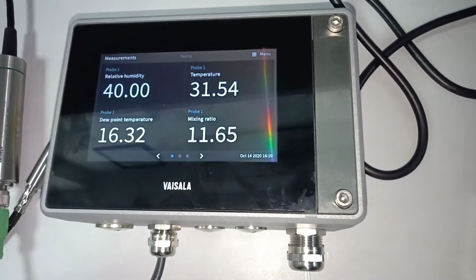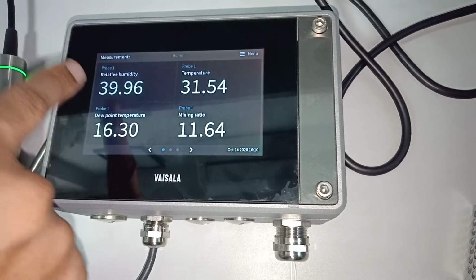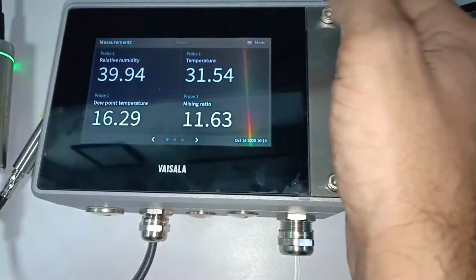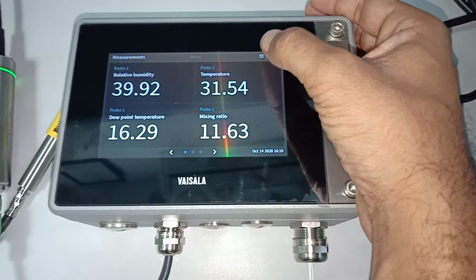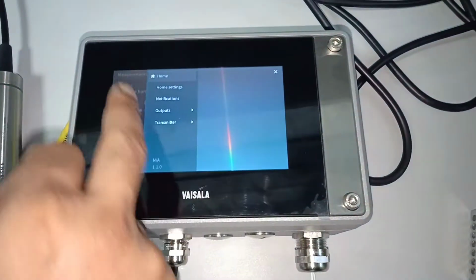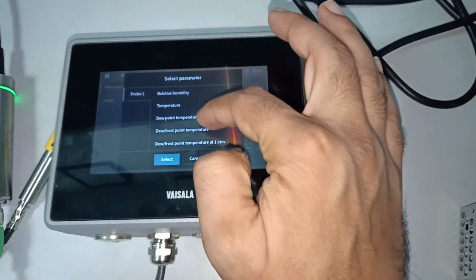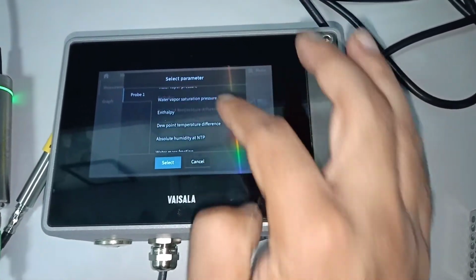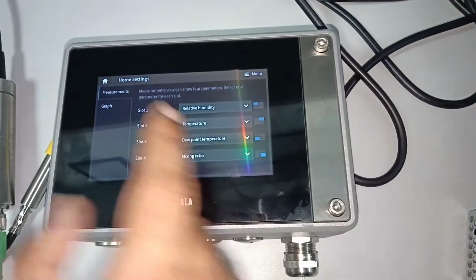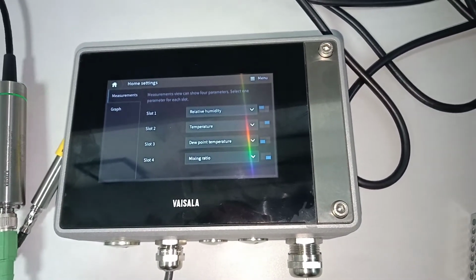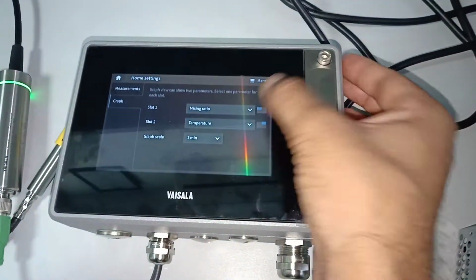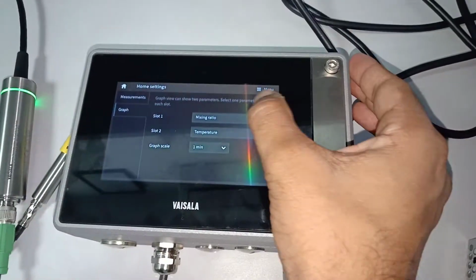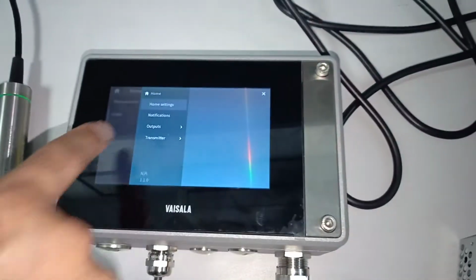You can see 4 readings at a time for one probe, but if there are 2 probes, then probe 1 you will get them labeled here, and probe 2 will show the different readings depending on what the measurements are. You go to the menu, you can set the parameters. So relative humidity, I can set any calculated parameter from relative humidity and temperature. So I have selected 4 parameters: relative humidity, temperature, dew point, mixing ratio. You can even plot the graph. So here I have selected mixing ratio and temperature. You can select any hygrometric parameter for which you want to plot the graph.